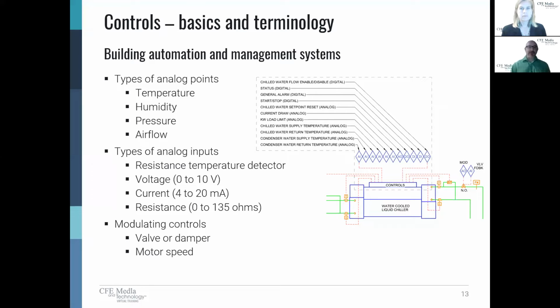An analog input is going to vary. It means that we can actually get a position or a temperature that's going to vary. And technically speaking, it's usually resistance or voltage or current. I can also have an analog output that I can modulate. So if I want to say a damper is 30% or 40% or 60%, I can change that. But that's not an on or an off. That is simply, I'm going to say I want it at a certain percentage. So 0 to 100%, that'd be an example of an analog type or modulating control.